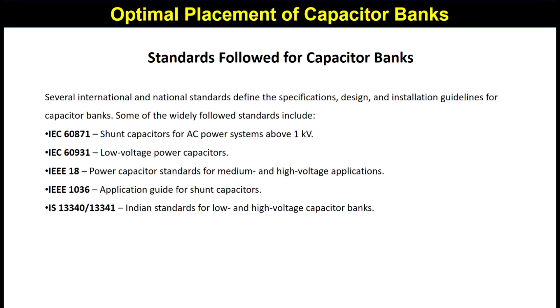Now, the standards followed for capacitor banks. Several international and national standards define the specifications, design, and installation guidelines. These include IEC 60871 for shunt capacitors for AC power systems above 1 kV, IEC 60831 for low voltage power capacitors, IEEE 18 for power capacitors for medium and high voltage applications, IEEE 1036 as the application guide for shunt capacitors, and IS 13340 and 13341 as the Indian standard for low and high voltage capacitor banks.